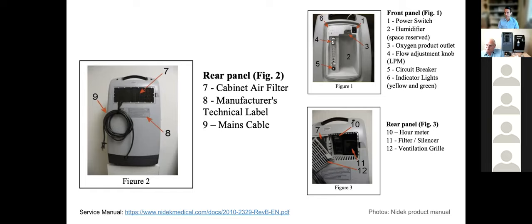The other thing to point out is that a lot of the components of the oxygen concentrator are the same. In the top right image, we have a flow meter, we have a power switch, we have the oxygen outlet, number 3. We also have number 5, which is a circuit breaker. These may be in slightly different locations depending on your unit. On the bottom right panel, you'll notice that we're looking at the back of this concentrator, and the air inlet filter has been removed, as has the plastic grill. And here is where the hour meter is found.